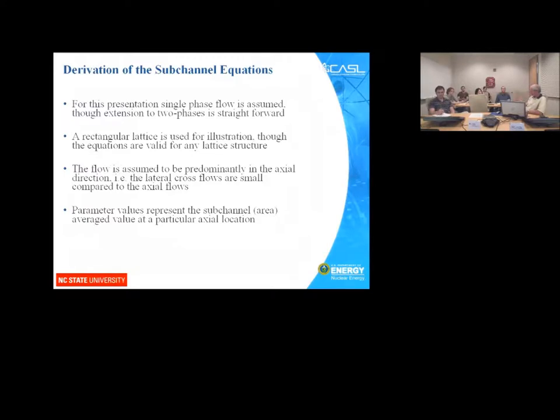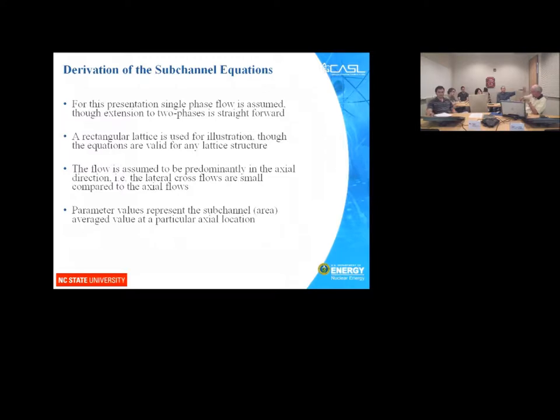I'm going to use the rectangular lattice for illustration. The equations we'll develop will have nothing in them which is lattice-dependent. They will contain things like the distance between sub-channels, cross-sectional areas, and gap spacings — parameters you can use to describe any lattice structure. All you have to do is specify in the input which sub-channel is connected to which, and what characteristics each sub-channel has, such as area.